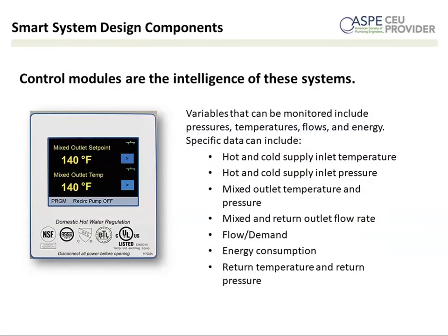So, talking a little bit more about the interface, every product is a little bit different. Some products may require a computer hookup. Other ones have buttons. In this particular instance, this is a touch screen interface, and it makes it very simple to access the information. It makes it very, very simple to set the valve up, to set the set point. If you have a pump tied to the unit, you can easily set up the return temperature that you would like and the parameters of when you want to turn the pump on and off.